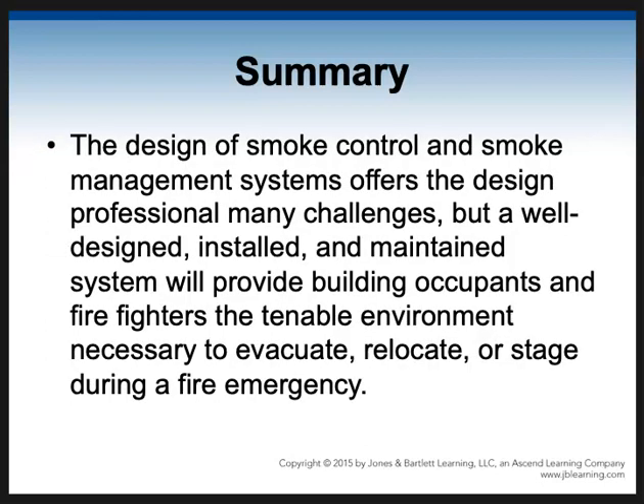Lastly, the design of the smoke control and smoke management systems is going to be done by a design professional, an engineer. Hey, we want the guy that graduated magna cum laude, the valedictorian of their engineering school that's designing these kind of things, because the way they're designed has a lot to do with the way they'll work. Then they need to be installed properly and maintained properly. The maintenance crews and the installation crews in the state of California, they have to be certified to do this kind of work. So they're going to provide the building occupants, the firefighters, a tenable environment necessary to evacuate, relocate, or stage during a fire emergency.